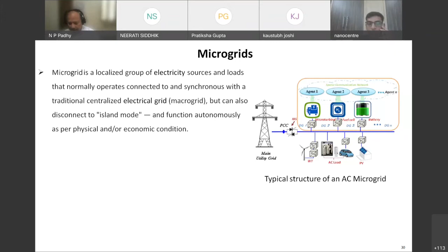Now the biggest challenge here: if the grid is not available to me, then my 2.8 megawatt of solar generation actually stops. They don't generate because they miss the reference point. That's why we need to think: if you increase excessive renewable energy to the grid, it is fine, but can we operate in both islanded and grid integrated mode comfortably and efficiently? Typically, if you can, that is a perfect AC microgrid.